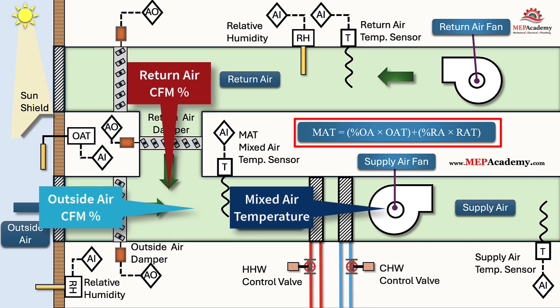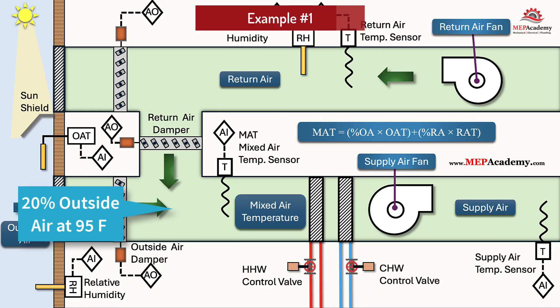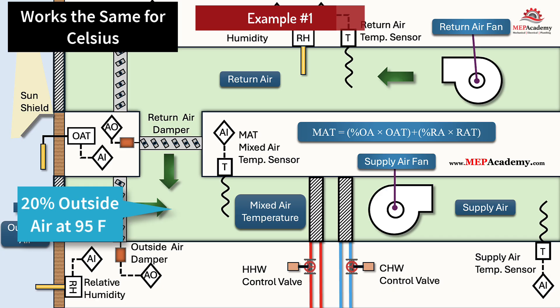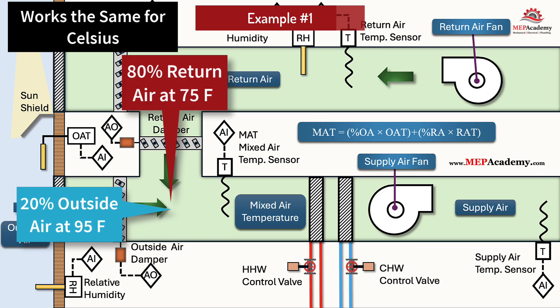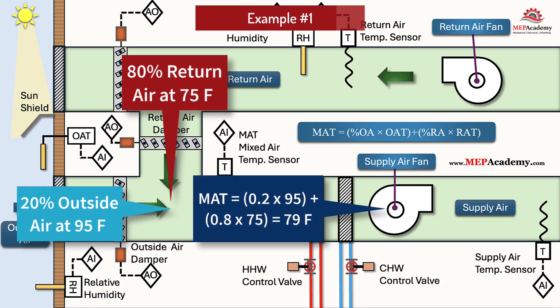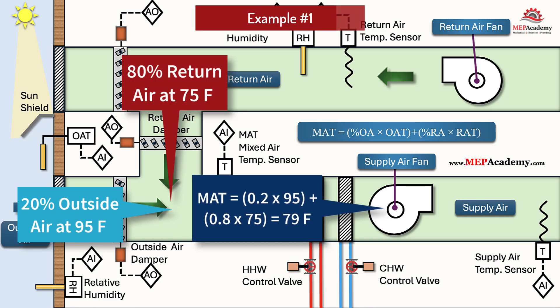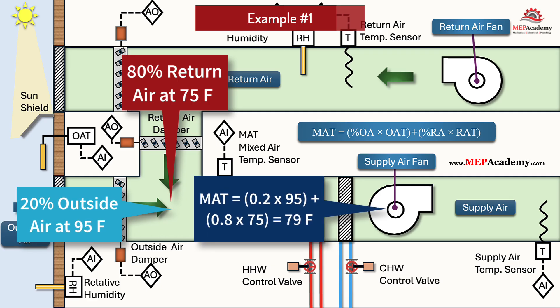Example 1 — 20% outside air: Outside air = 95°F, return air = 75°F, outside air = 20%, return air = 80% of total air volume entering the mixing box. Mixed air temperature = (0.2 × 95) + (0.8 × 75) = 19 + 60 = 79°F. The coil sees 79°F entering air.